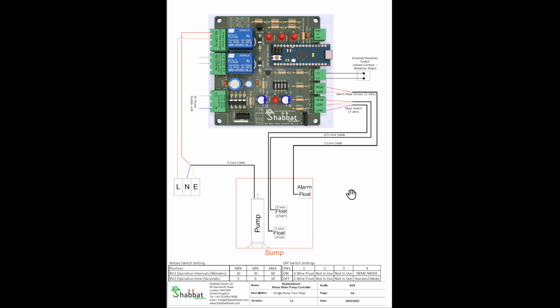Shabbat Smart Waste Pump Controller, a setup with a single pump and a twin float. So here we have the sump, we have a pump, high level float, low level float, and water alarm level float. The floats are connected on the controller, the high and the low with a common for both of them. This will activate the pump at high and deactivate when it reaches the low level.